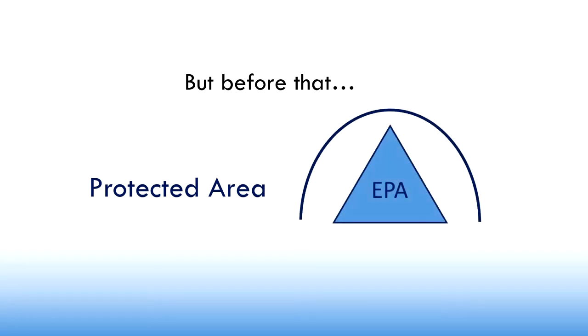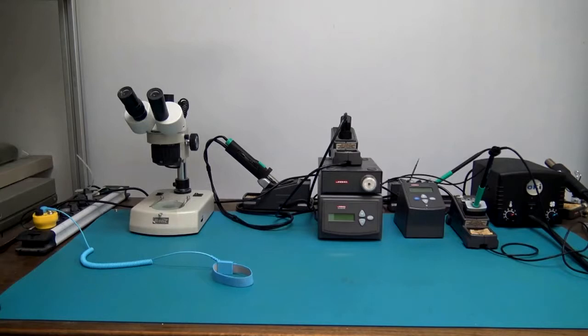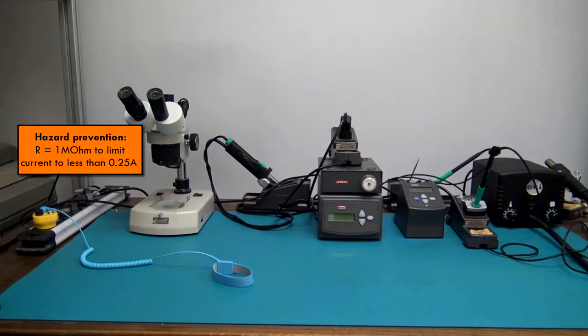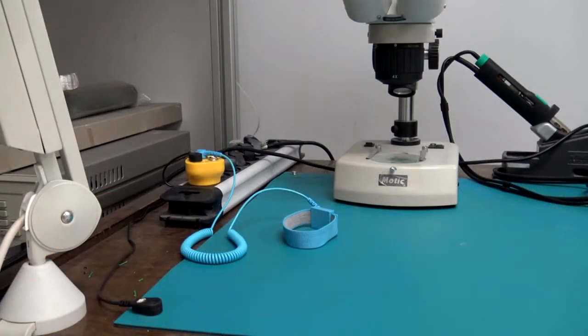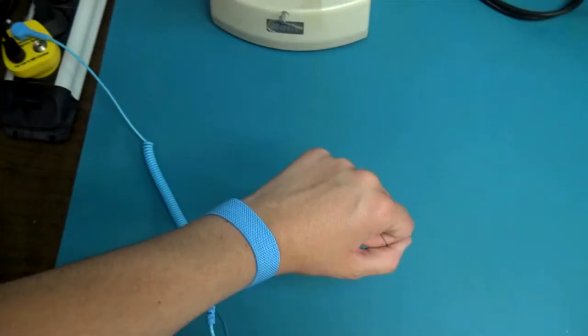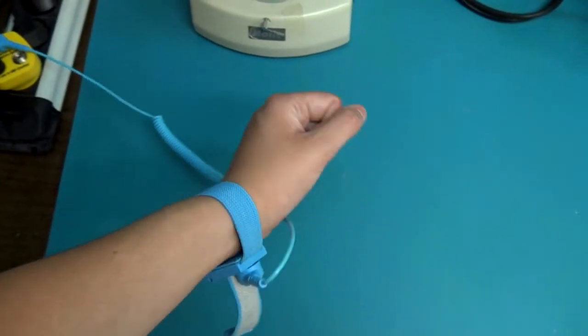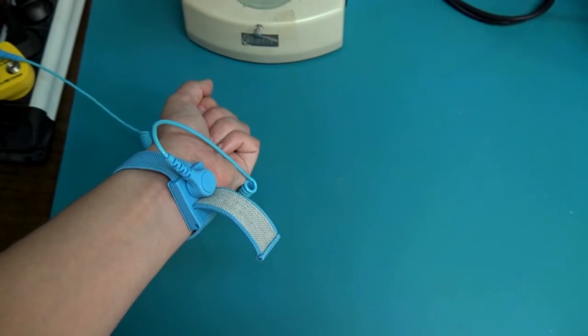Before that, we have to set a protected area — an EPA — where we are going to work with sensitive components. Here we have our EPA, with an anti-static surface and a wrist strap connected to a common ground point, where we connect all the conductors to. We have also removed the insulators from the area. The wrist strap is used to ground personnel, as we can see in this video.